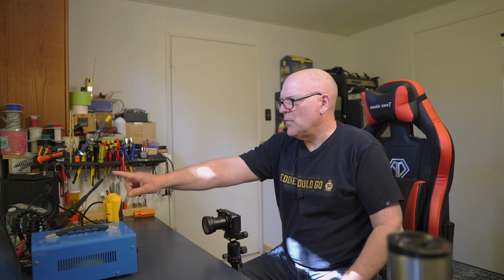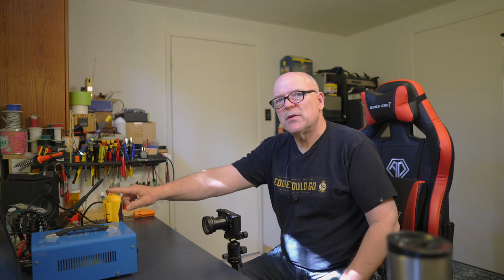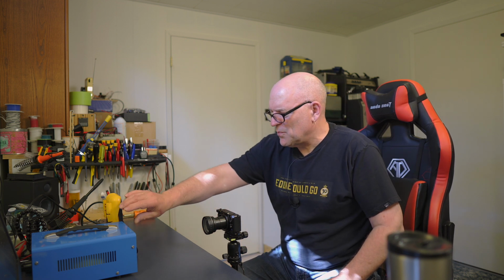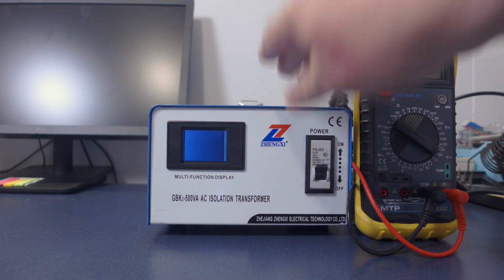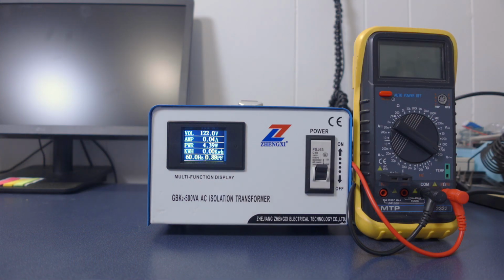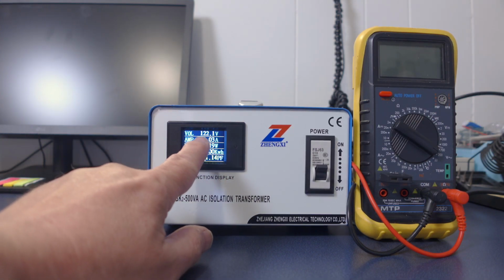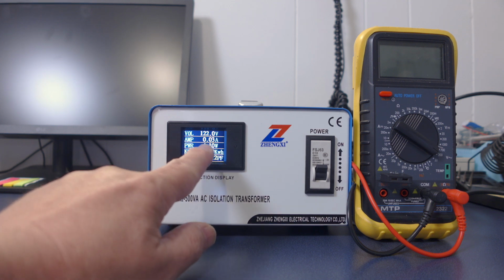Well, I've set up the ISO transformer on the bench. It's turned off right now. I have connected my multimeter to the outputs on the back just so that we can see that we're getting voltage out of the back. There's not really much else to display or show. Nothing super sexy here, folks, but we can see it turn on and see what the display tells us. So there, we turn it on. It gives us incoming voltage, 122.1 volts right now.